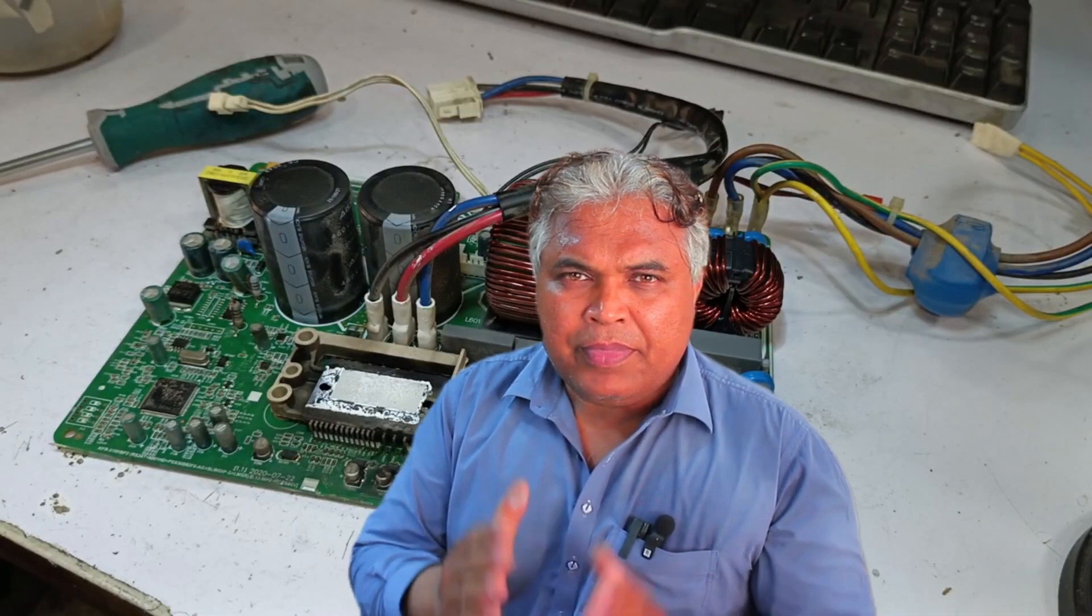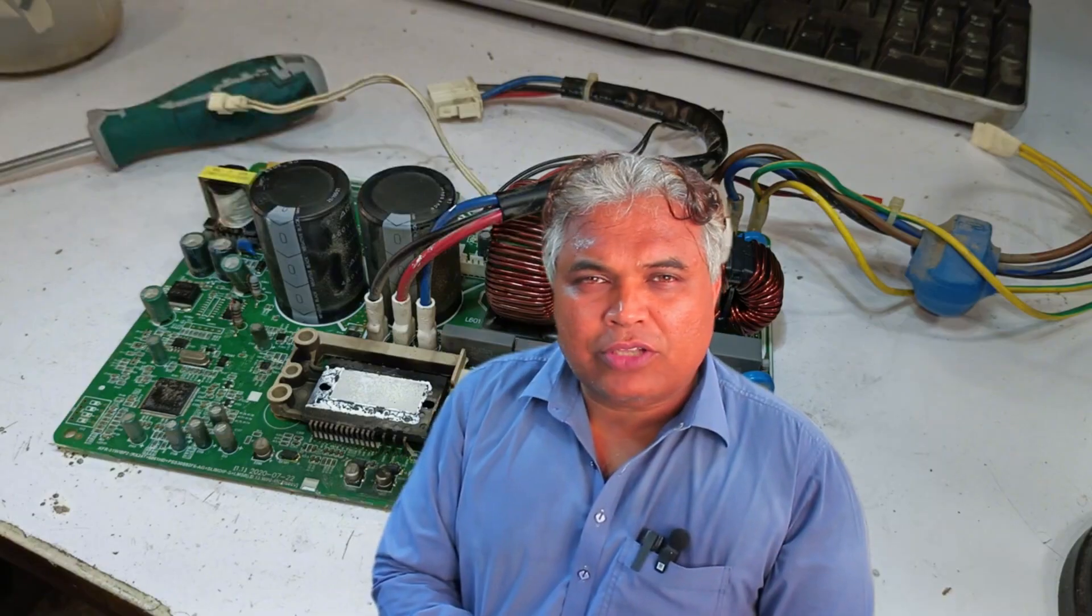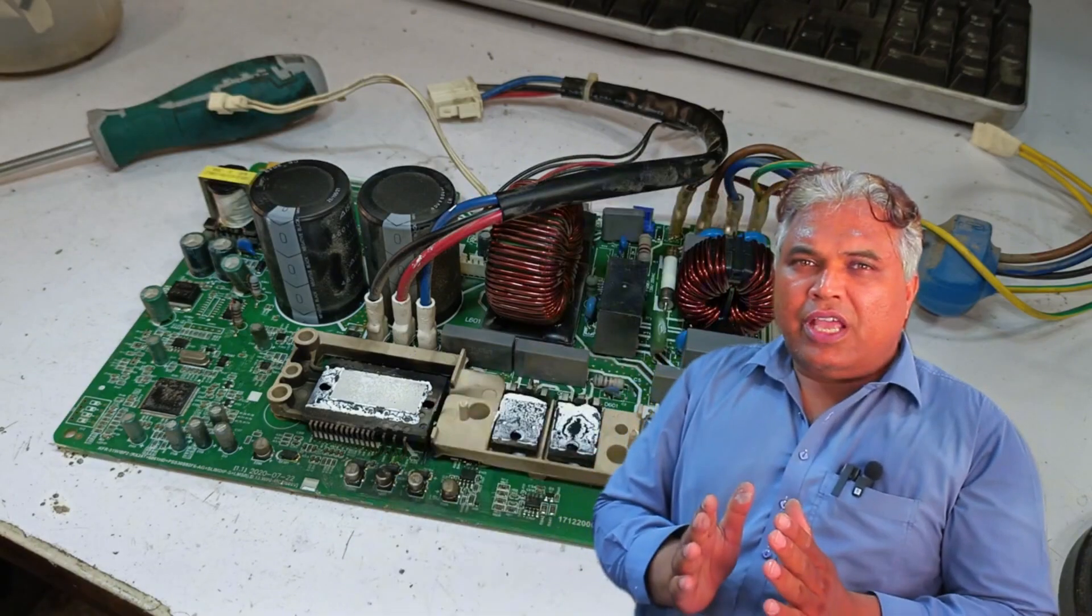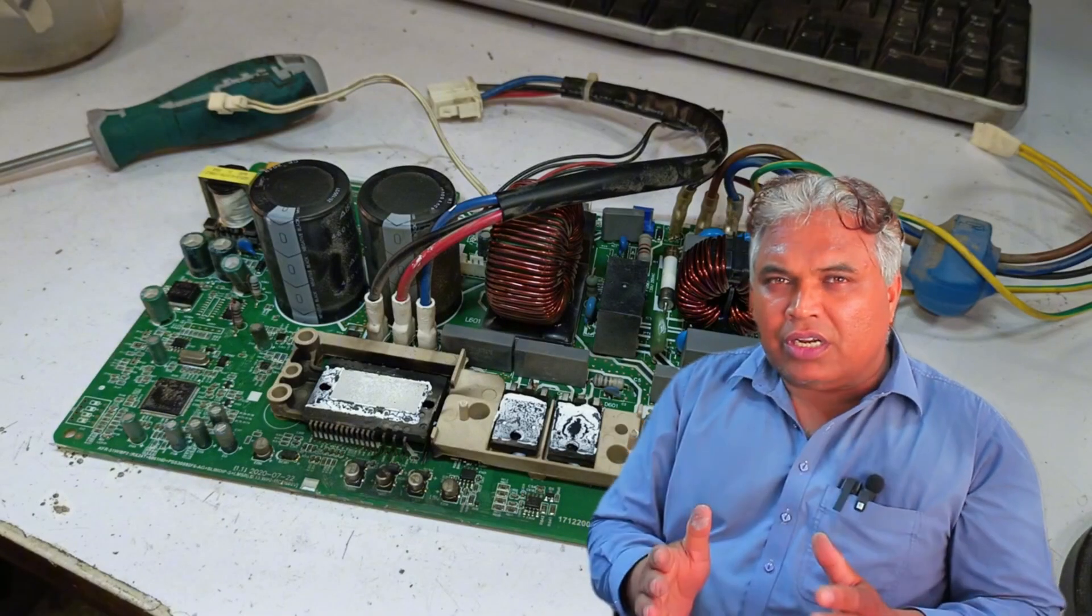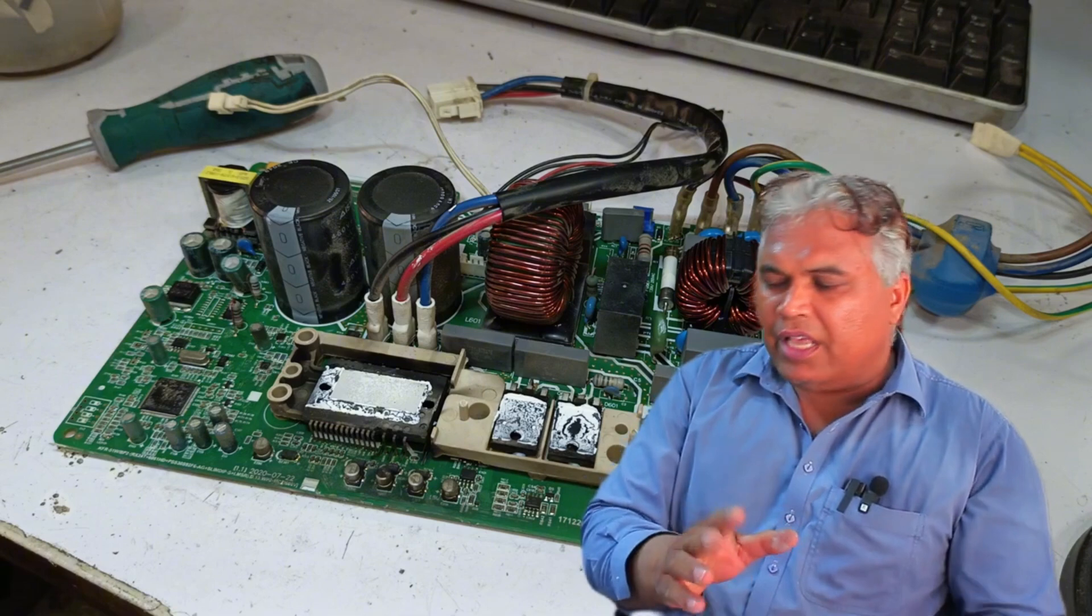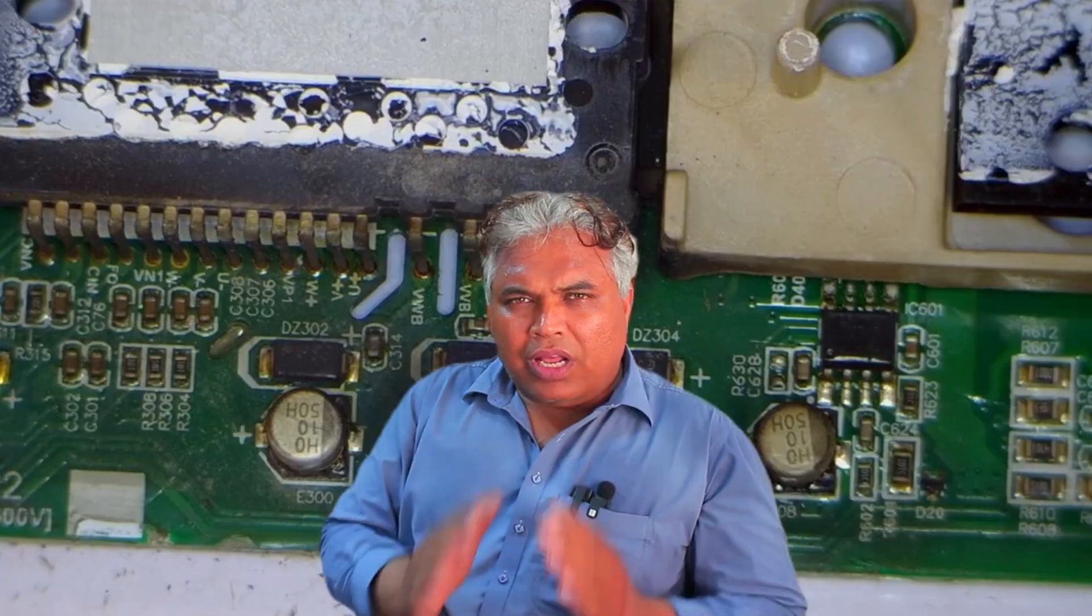The issue arose because the customer washed the unit with a pipe, and after washing, the P0 error started appearing. When you service a unit and don't remove the indoor or outdoor PCB, there's a chance that water can get inside. If you turn it on immediately after washing, there's a possibility that it could get damaged. This is what happened here as well.